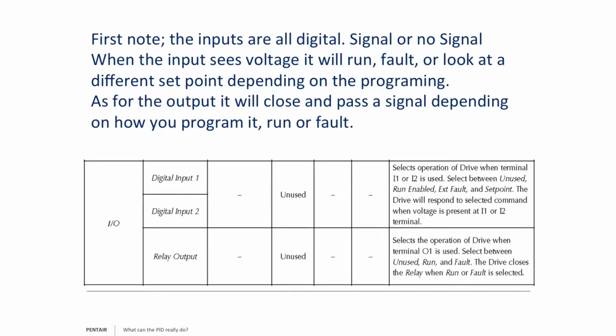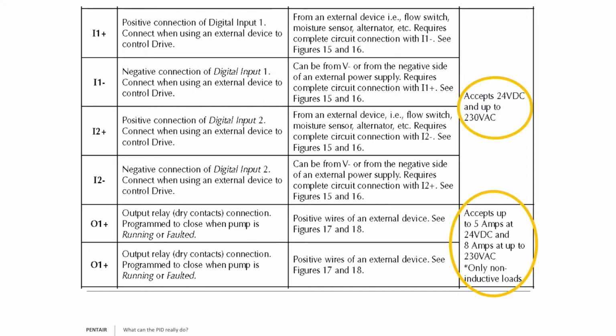meaning that there's either voltage or no voltage, a signal or no signal, on or off. So when the input sees voltage, it's saying, okay, I see the voltage being applied or I see the voltage removed. What do you intend for me to do? For example, when it sees current, are you trying to tell it to run, fault, or look at a different set point? Looking in the manual, we tell you exactly what digital inputs 1 and 2 can do. What you have to decide is what you intend it to do.